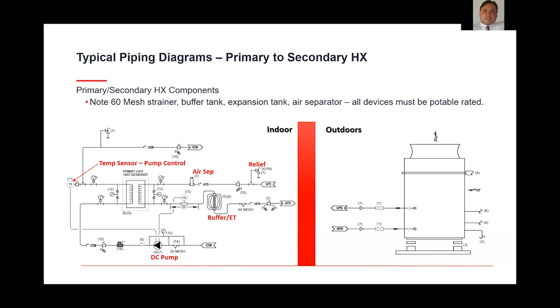jumping into some of the finer details of the application and the specialties I mentioned before. I'm going to look at this with a little bit more granularity, when we start looking at these piping requirements and specialty requirements between the outdoor unit and indoor. Outdoors, you're dealing with basically 2 pipes, supply and return. Typically, these are going to have to be heat traced.